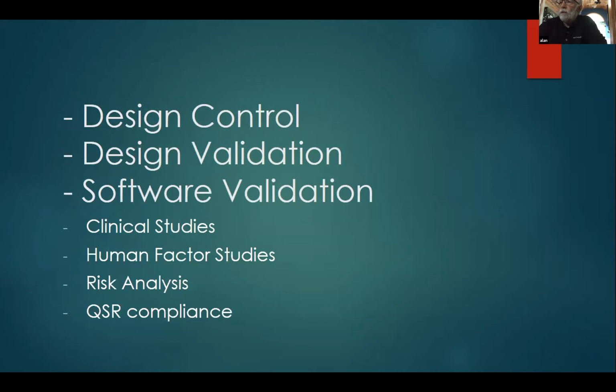When you're developing devices for dealing with FDA, you have to make sure that you are following the FDA design control procedures and the quality system regulations. We run into a lot of companies where they're developing a lot and they're not keeping the records the way the FDA expects them to keep those records. And then they have to go back and reproduce it. They have to go backtracking and figuring out what the inputs were and what the outputs were and how it was going to be verified and validated. So you really should have your design control procedures in place and follow those procedures as you're developing a device, instead of having to go back and reconstruct it. We've seen that a lot.